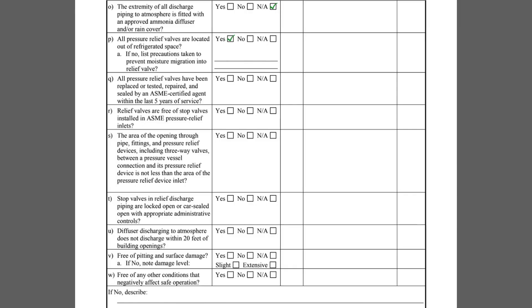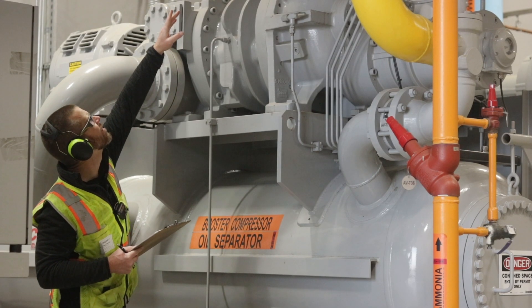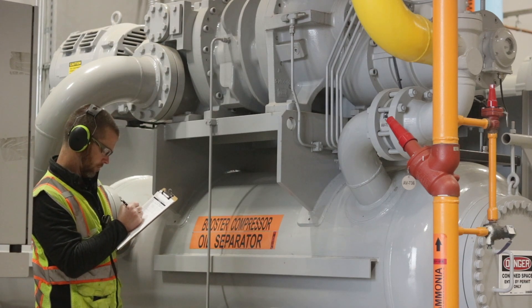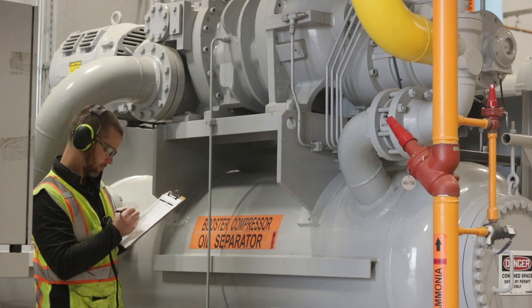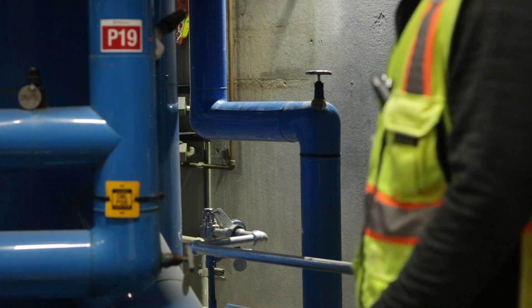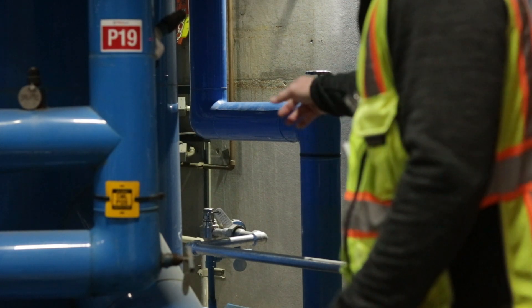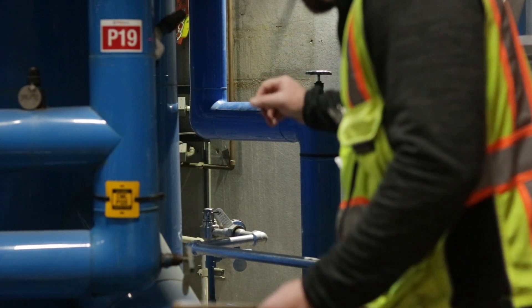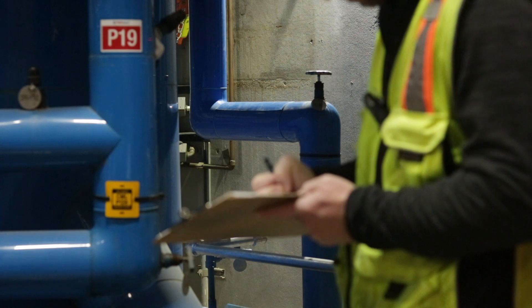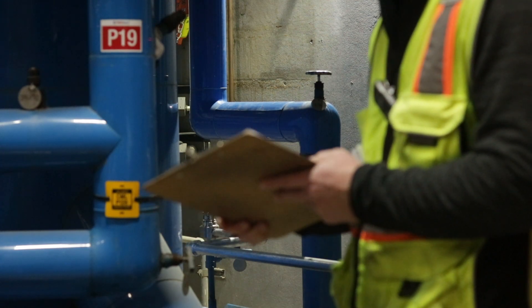Relief valves should be located outside of the refrigerated space. Item P asks if this is true for the relief system being inspected. If the answer is no, the inspector must indicate what measures are being taken to prevent moisture in the air from condensing and migrating into the relief valve spring.